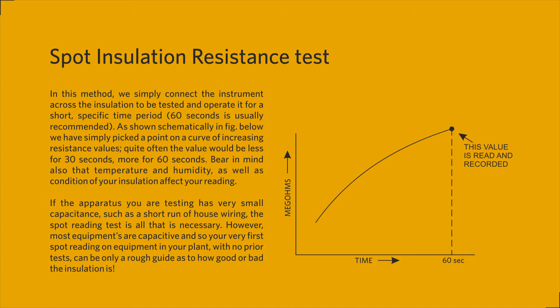Spot insulation resistance test: In this method, we simply connect the instrument across the insulation to be tested and operate it for a short, specific time period — 60 seconds is usually recommended. We have simply picked a point on a curve of increasing resistance values. Quite often the value would be less for 30 seconds, more for 60 seconds. Bear in mind that temperature, humidity, and condition of your insulation affect your reading. If the apparatus has very small capacitance, such as a short run of house wiring, the spot reading test is all that is necessary. However, most equipment is capacitive, so your very first spot reading with no prior tests can be only a rough guide as to how good or bad the insulation is.